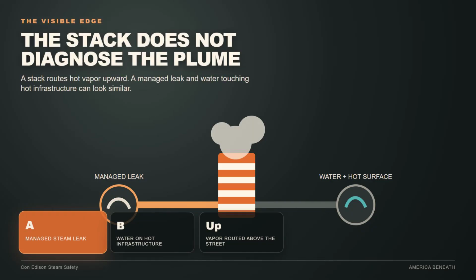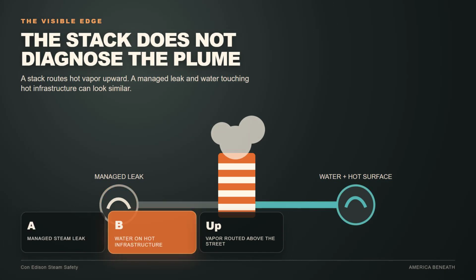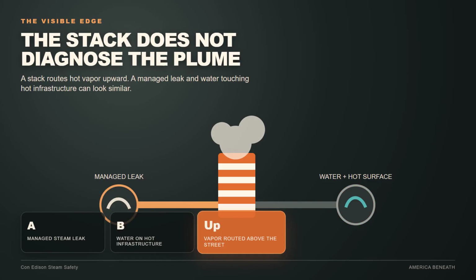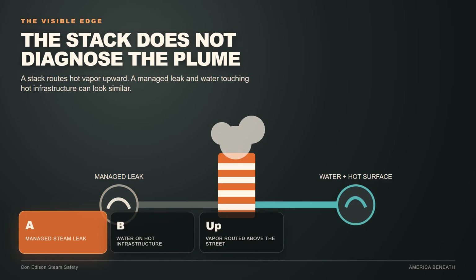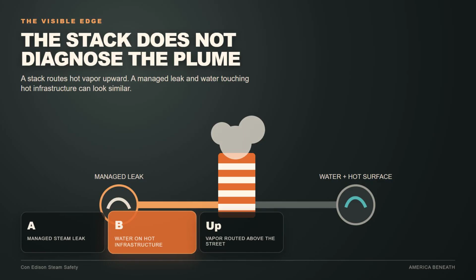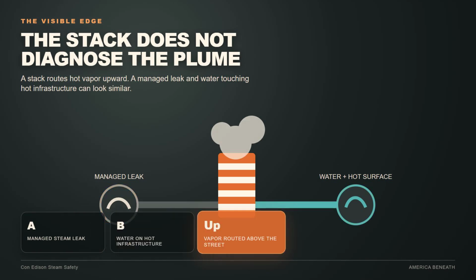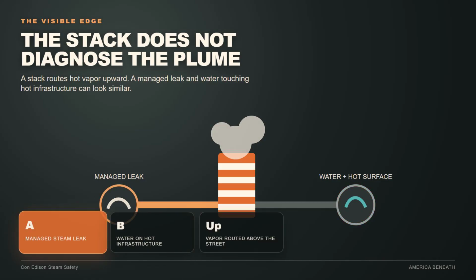The stripe stack is the network's most visible object, but it is easy to read it incorrectly. The stack's job is to redirect hot vapor above pedestrians and traffic. It creates separation between street level and whatever is producing the visible plume below. One possible source is a steam leak that the operator is managing. Another is ordinary water reaching very hot steam pipes or hot surfaces inside a manhole. Rainwater, a water main leak, or other street water can heat rapidly and become a large cloud of visible vapor. From a distance, both paths can produce the familiar New York image. That does not mean every plume is harmless, and it does not mean every plume marks a broken steam main. The stack tells you that hot vapor is being moved upward. It does not diagnose the cause by itself.